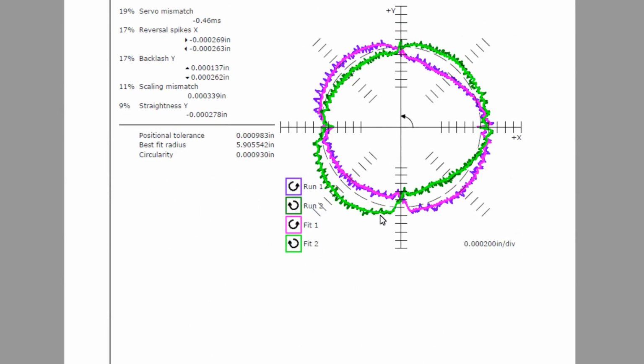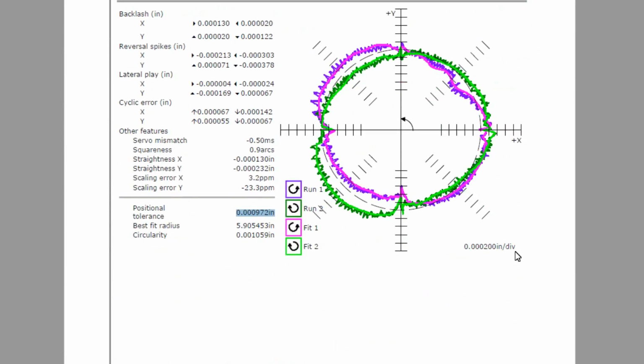Notice how much this deviation was in the plot before - we can compare it and see how it's much less here. We were able to dial in the backlash pretty good, but notice these spikes you've got here? That's the backlash comp working. So while we reduced the backlash, we increased the reversal spikes slightly - not a lot, but slightly. It's better than having the backlash in there.